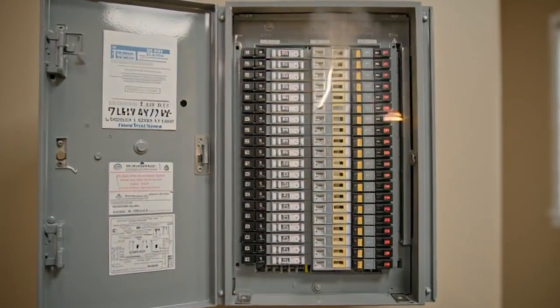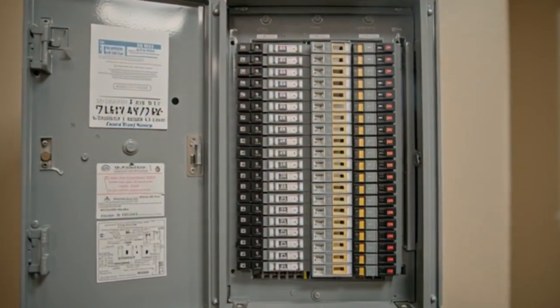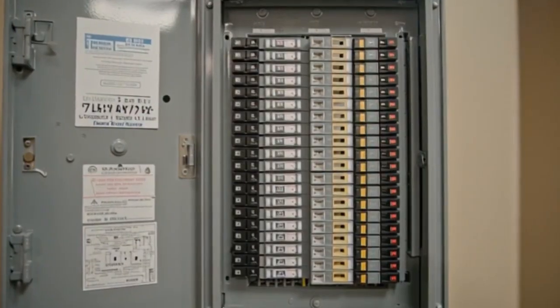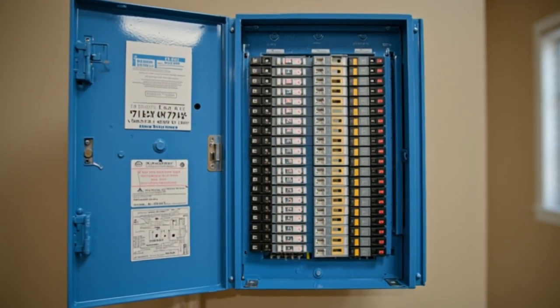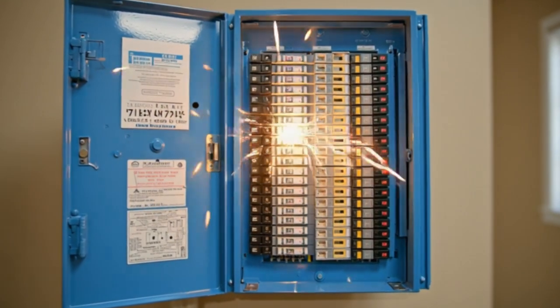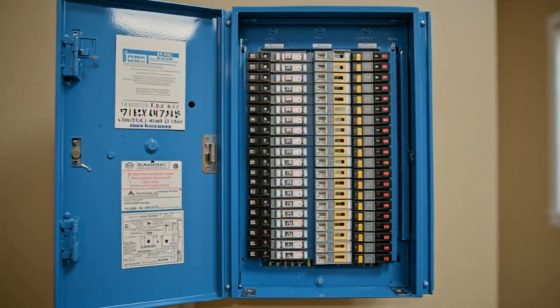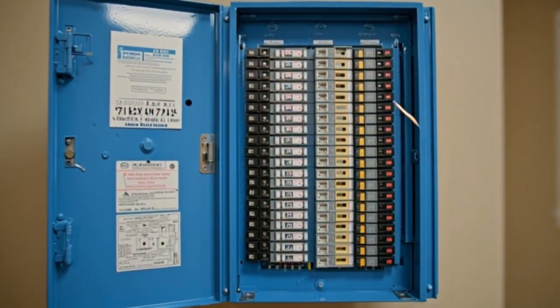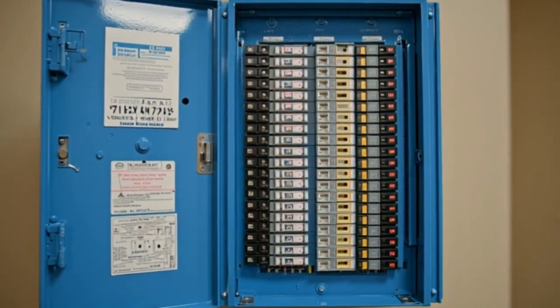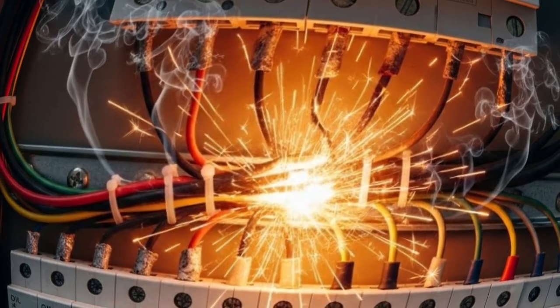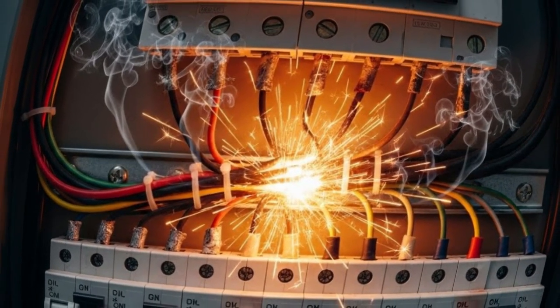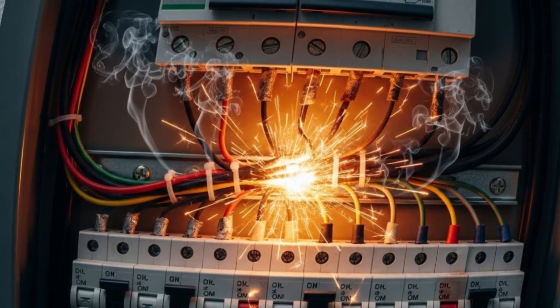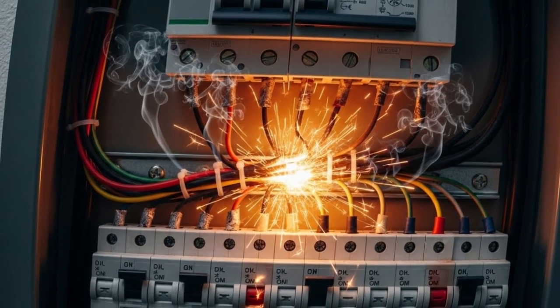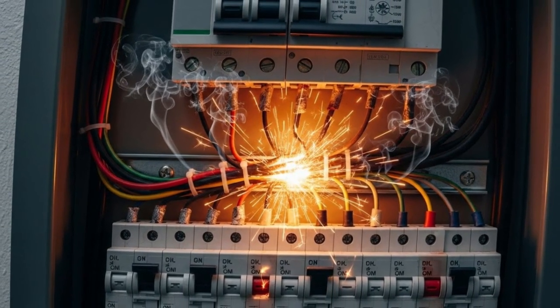Short circuits usually trip individual branch circuit breakers, but under certain conditions, a short circuit can trip your main breaker instead. This happens when the short is severe enough to spike total current above the main breaker's threshold before the branch breaker can react. It also happens when the short circuit exists in the wiring between the main breaker and the branch breakers, an area protected only by the main breaker itself.